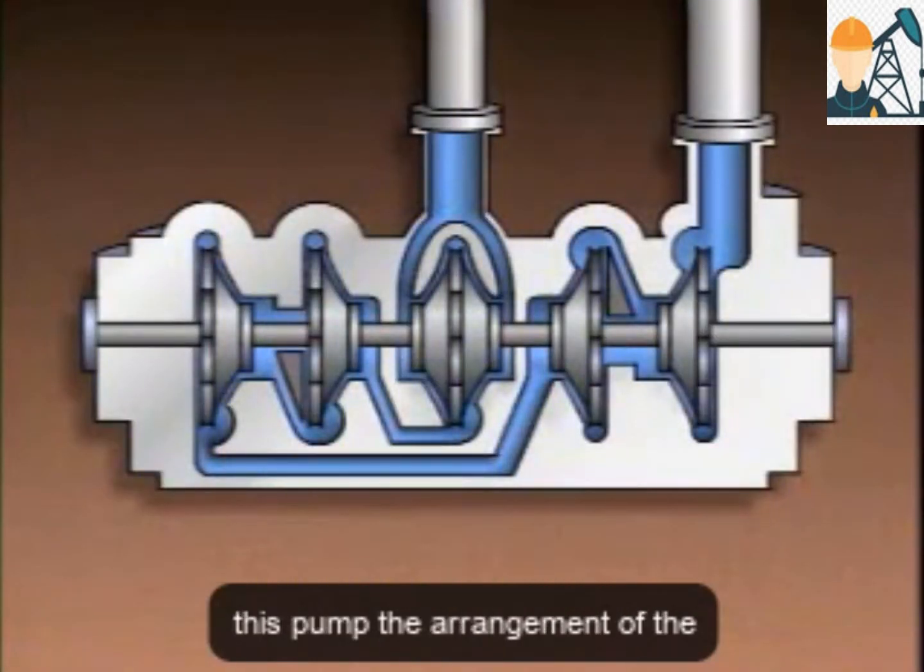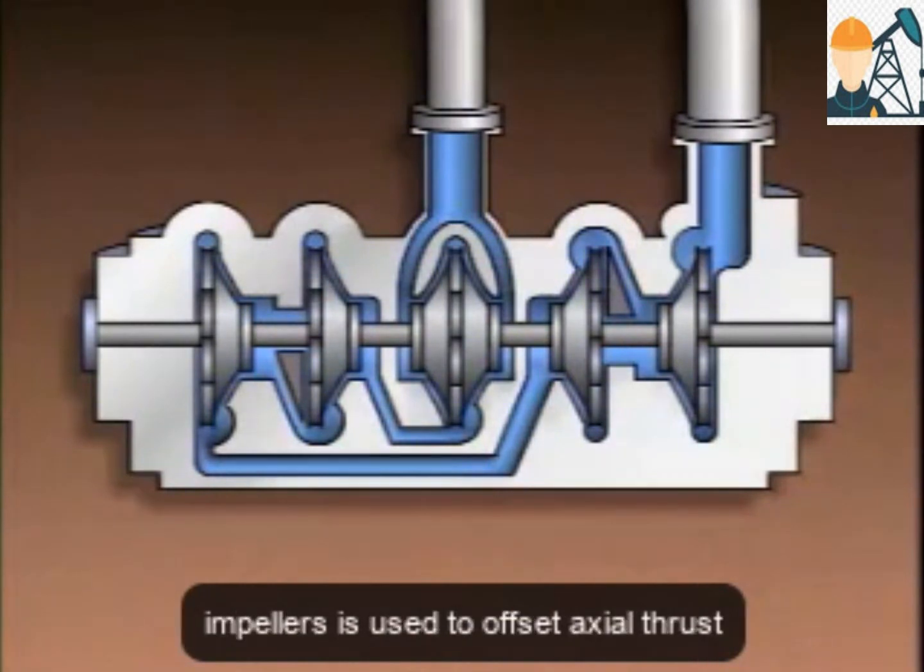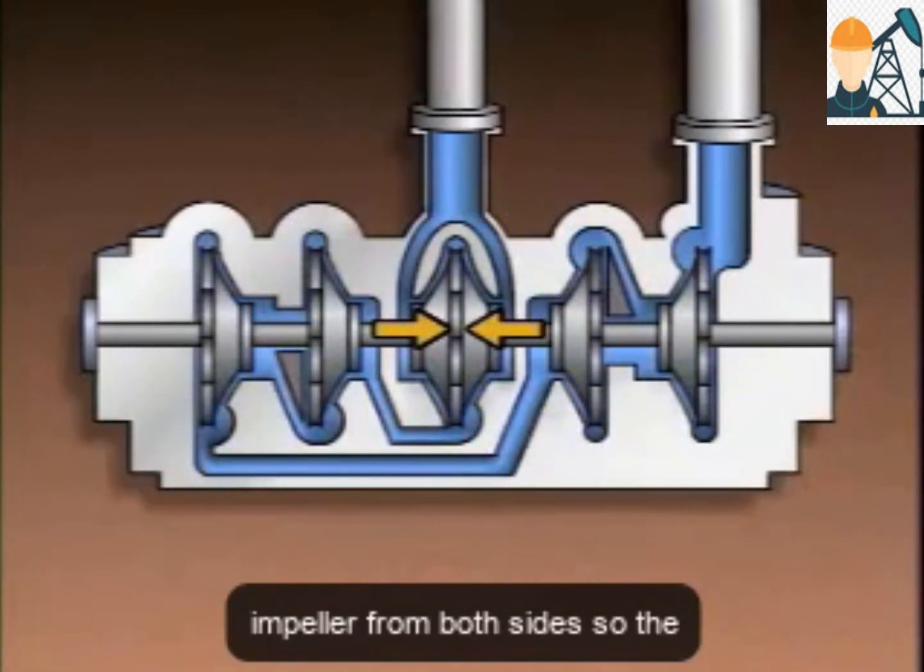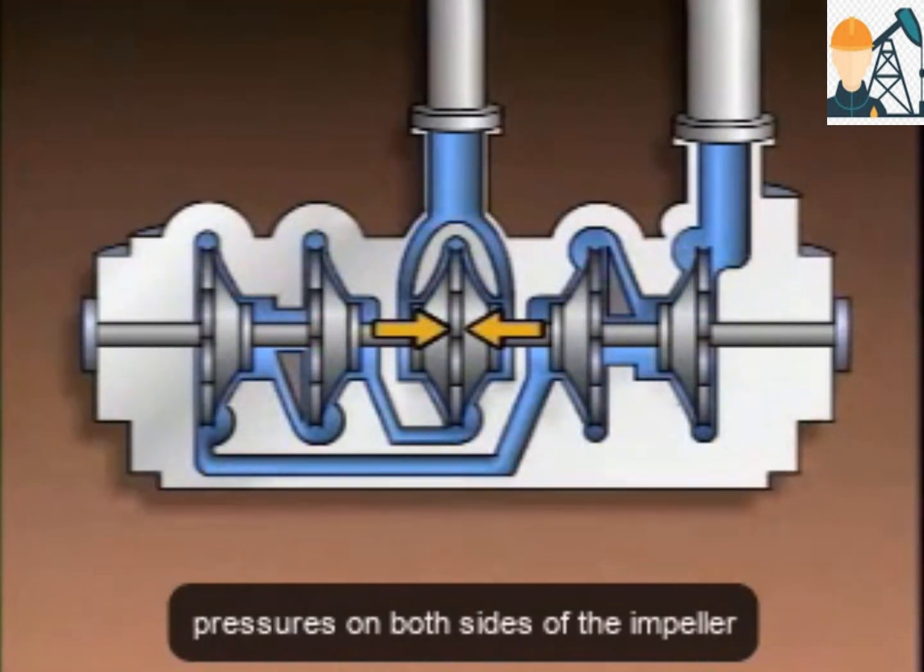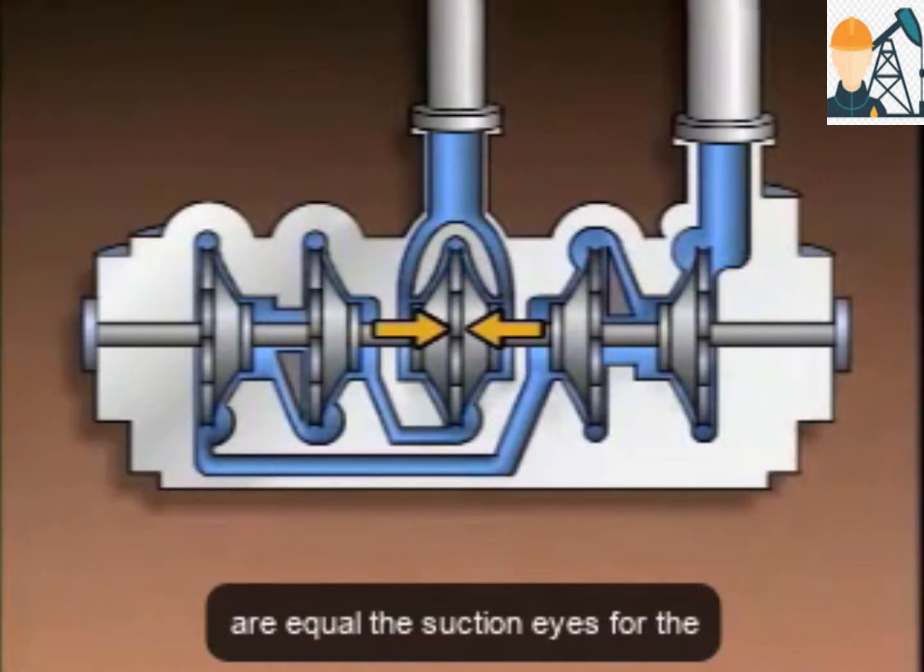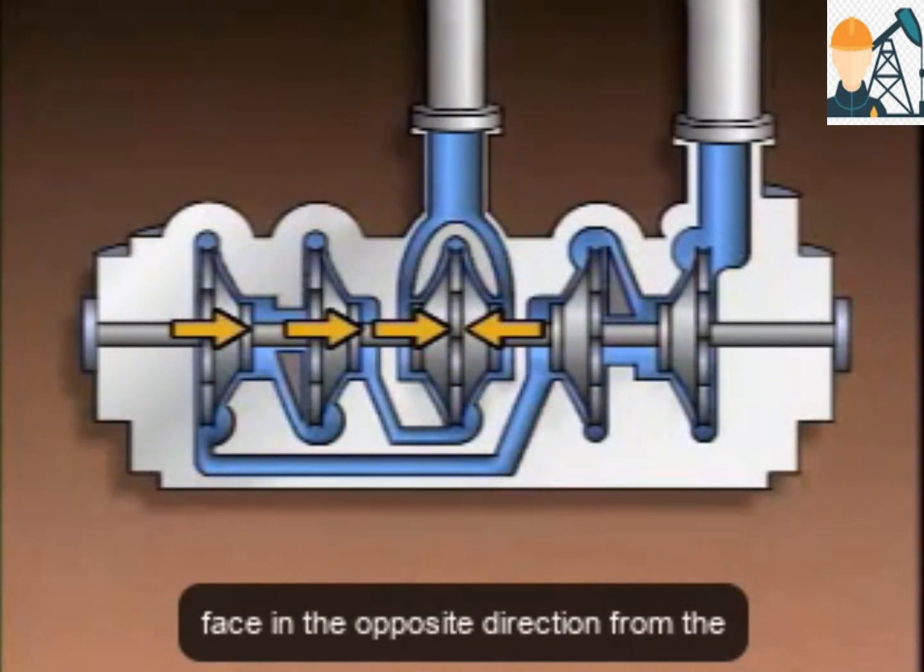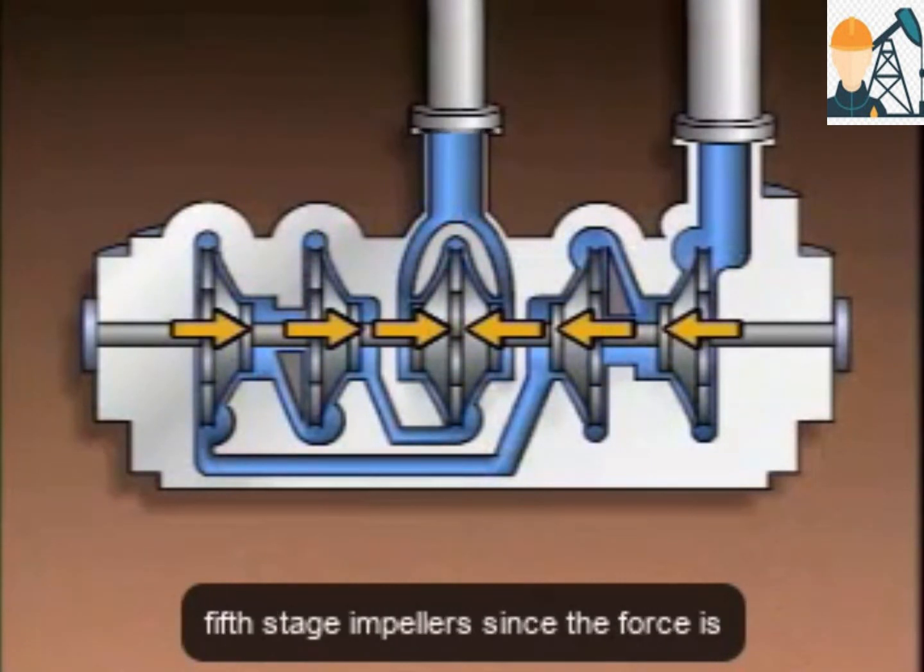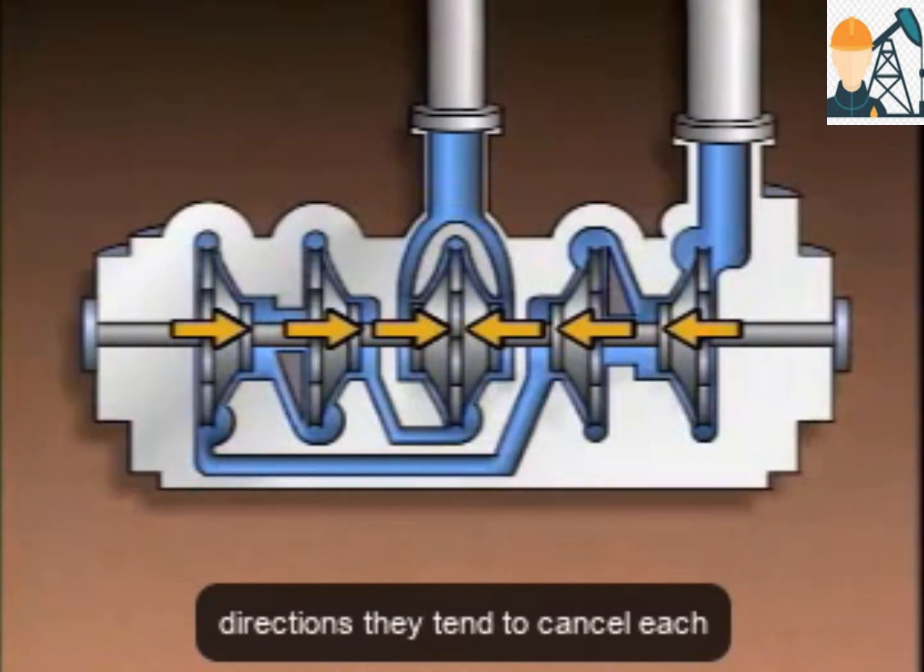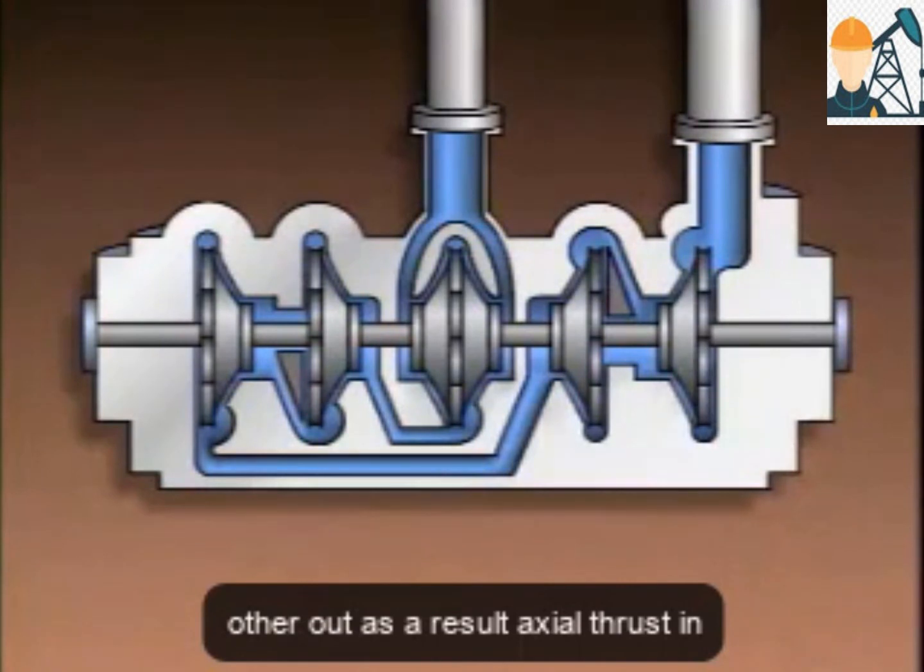Now, on this pump, the arrangement of the impellers is used to offset axial thrust. Processed liquid enters the first stage impeller from both sides. So, the pressures on both sides of the impeller are equal. The suction eyes for the second stage and third stage impellers face in the opposite direction from the suction eyes of the fourth stage and fifth stage impellers. Since the forces caused by axial thrust are in opposite directions, they tend to cancel each other out. As a result, axial thrust in this pump is kept to a minimum.